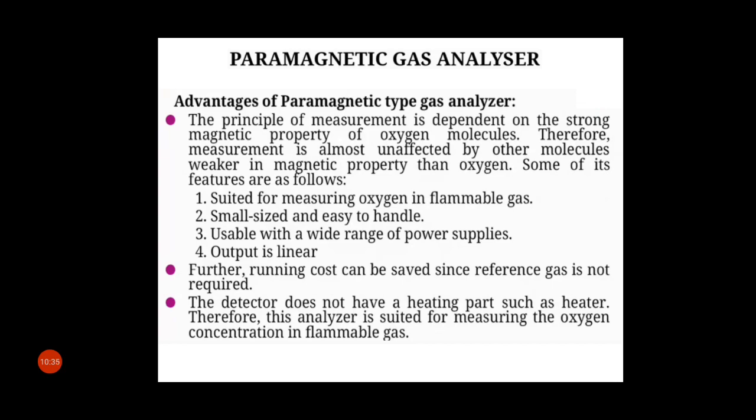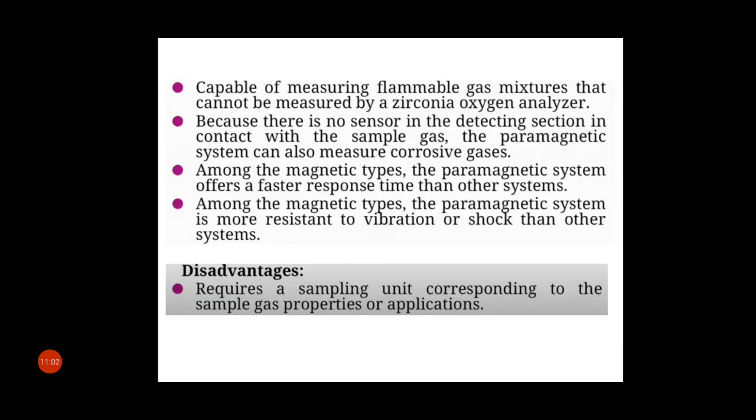Therefore, this analyzer is suited for measuring the oxygen concentration in flammable gas, because we have seen that the zirconium gas analyzer is not suited for measuring oxygen concentration in flammable gases. But the paramagnetic gas analyzer is suited for measuring the oxygen concentration in flammable gas. Next, it is capable of measuring flammable gas mixtures that cannot be measured by a zirconia oxygen analyzer.